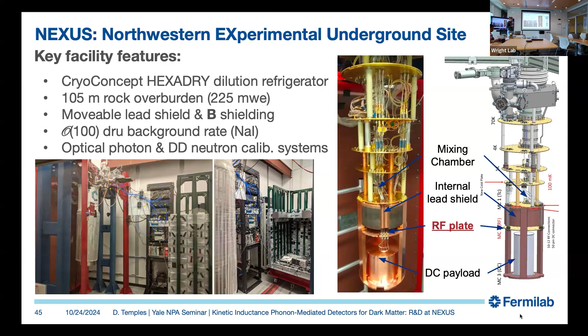Our rock overburden at NEXUS gives us 225 meters water equivalent shielding. We additionally have this movable lead shield, so there are lead bricks behind this wall, and we can bring the shield in. Between the shield and this internal lead plug, we get 4 pi coverage for our detector payloads from the shielding. Additionally, we have some magnetic shielding externally and at the 4 Kelvin stage of the fridge. We have optical photon calibration systems, and we are now commissioning our deuterium-deuterium fusion neutron generator so that we can do nuclear recoil calibrations in a low background and cryogenic low background environment.